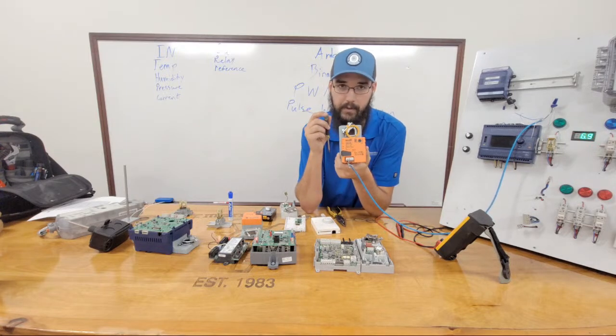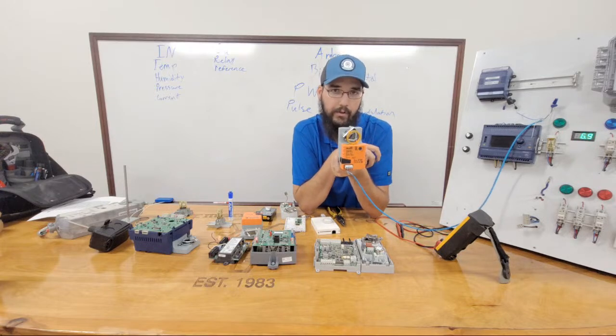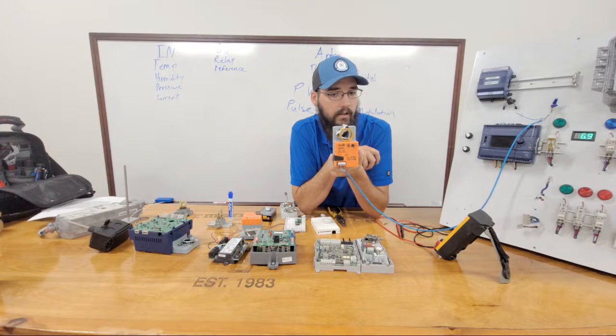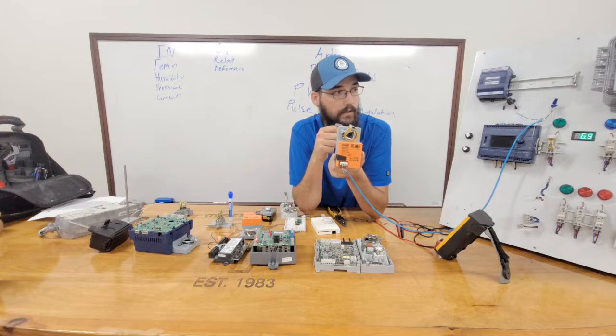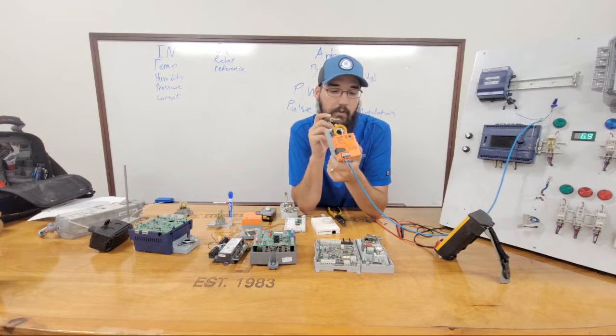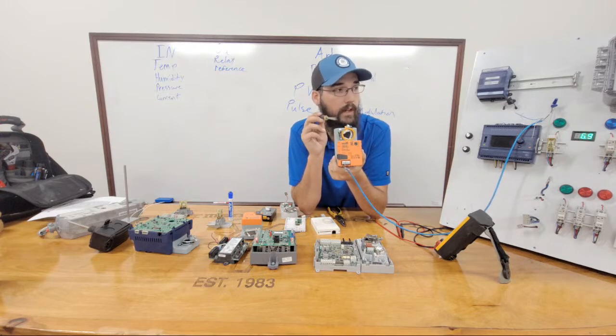So if I flip it, and it's just what, 1/8 of a turn is all it takes. Now I haven't done anything to change the input signal. I still have 0 volts DC coming in. But if you watch, I'm moving. And so that's what that black dial is for, is so that you can properly set what you want the rotation to be.